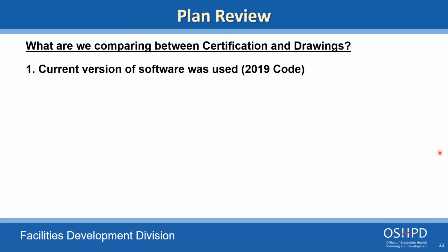So what are we comparing between the certificate, certification, and the drawings? The current version of the software used, making sure it's applicable to the code cycle in force right now, in this case the 2019 code, so you're not using an old version when doing the calcs.